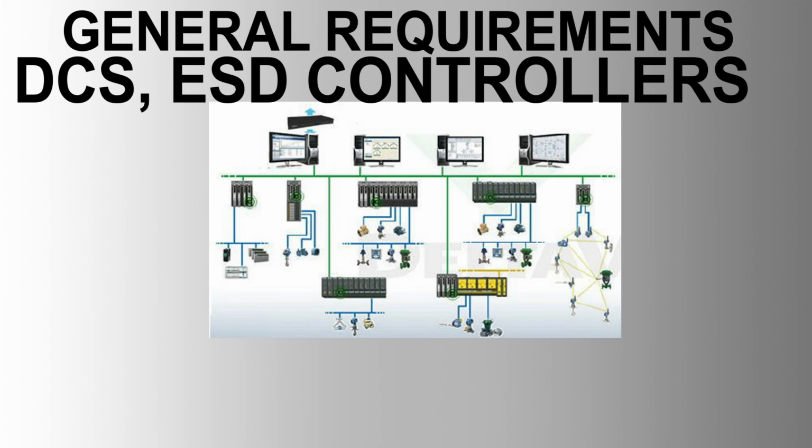9. ESD interfaces to packaged equipment. Direct interface. ESD systems should interface directly with packaged equipment, such as compressors, pumps, and turbines, to ensure coordinated shutdown in case of emergency. Use hardwired signals and standard communication protocols to exchange critical safety and operational data.